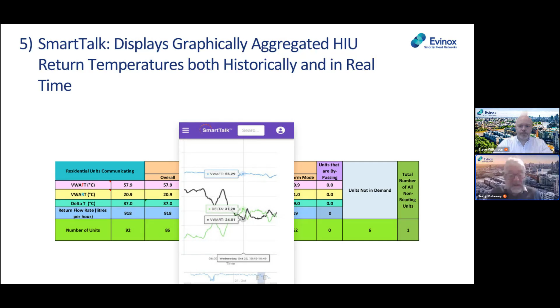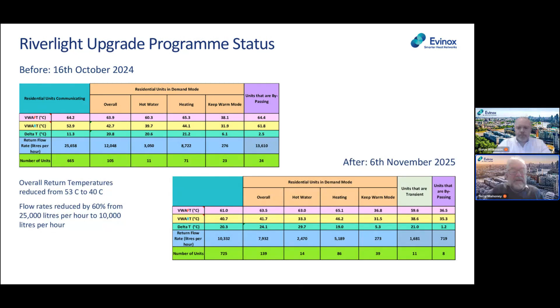As Steve mentioned, the Riverlight project, over a period of around 12 months, involved practical apartment HIU upgrades and refinements using the Smart Talk interface I've touched on. We've been able to reduce overall return temperatures from 53 degrees to 40, and also reduce flow rate through the heat network by 60%, from approximately 25,000 litres an hour to about 10,000 litres an hour.